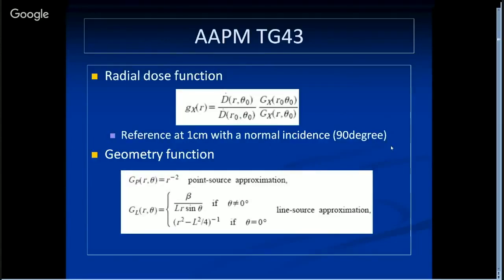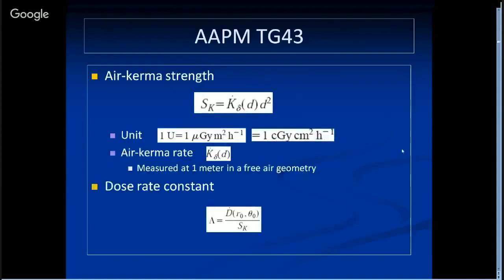This report also defines the radial dose function and the geometry function, and defines the source strength and its unit. When we have the source strength, we can get the dose rate constant lambda at the reference point, 1 cm away from the center line at 90 degrees.